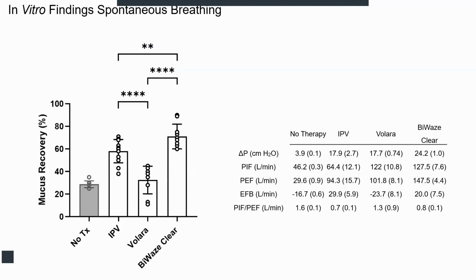So with our in vitro findings, first I want to call out the delta pressures. The delta pressures are going to be the difference between baseline and PIP. So the total delta pressures, the peak and the trough, those are going to be reflected here as no therapy. That's just during spontaneous breathing. So we're only generating a small transpulmonary pressure here. These are the flows that we're generating during inhalation and exhalation. This shows the expiratory flow bias. Basically, you take this value minus that value, and that's what you get. And then if you express them as a ratio, peak inspiratory flow over peak expiratory flow, we see that that's 1.6. And the lower you go, the more effective secretion management or mobilization will be, because you have more of this expiratory flow bias.